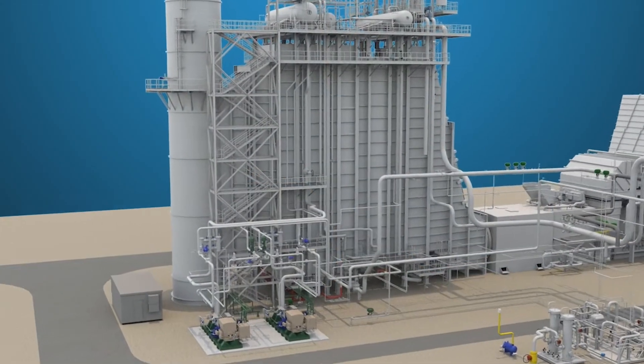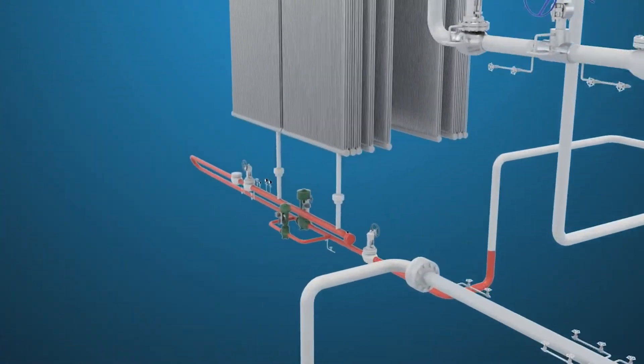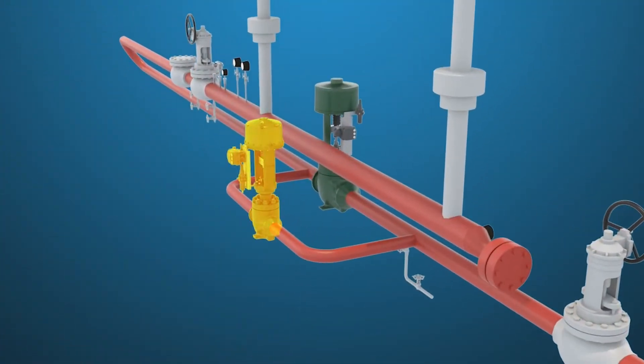Once the feed pump operation is stabilized, the HP drum will be filled using the feed water startup valve. The valve is sized to provide the flow rate required to fill the drum in the time specified by the plant designer.